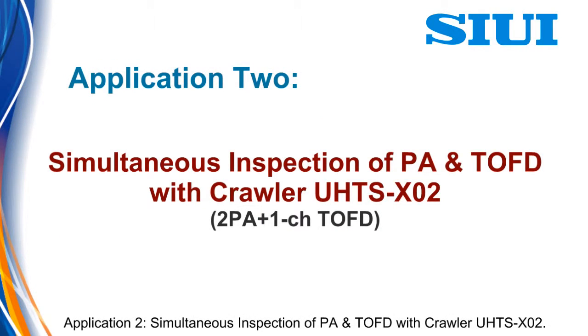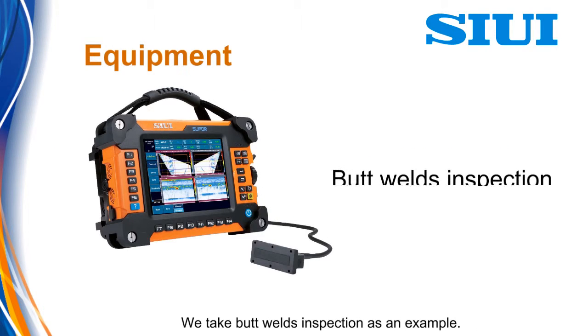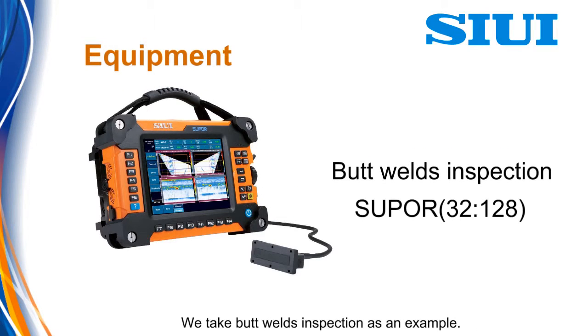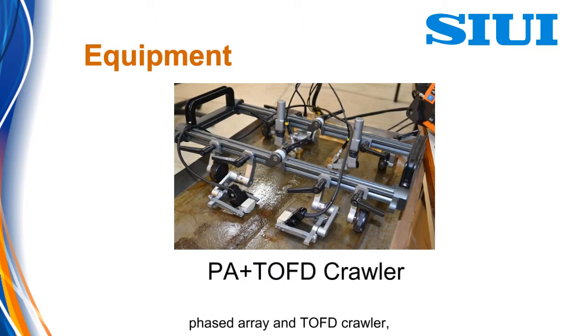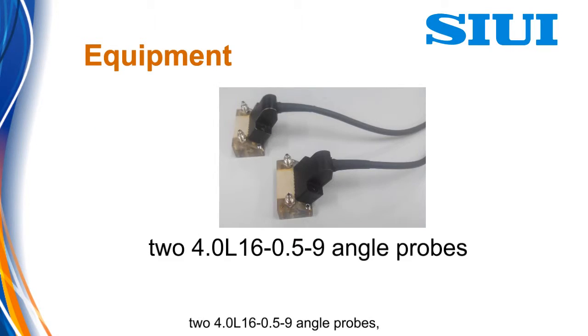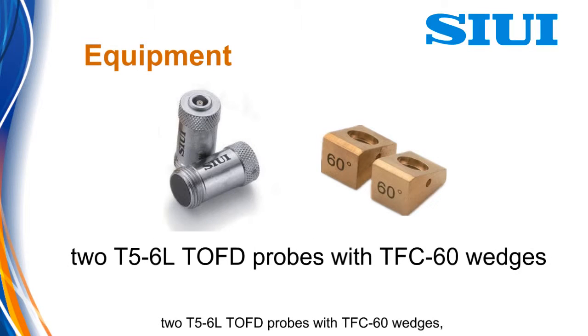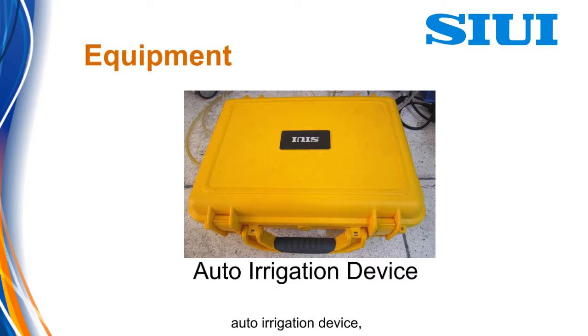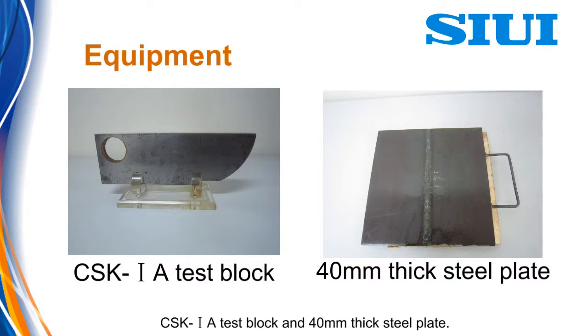Application 2. Simultaneous inspection of PA & TOFD with crawler UHTS X02. We take butt welds inspection as an example. In this inspection, we use Super phase array and TOFD crawler, two 4.0L16-0.5-9 angle probes, two T56L top probes with TFC60 wedges, auto irrigation device, CSK1A test block and 40mm steel plate.